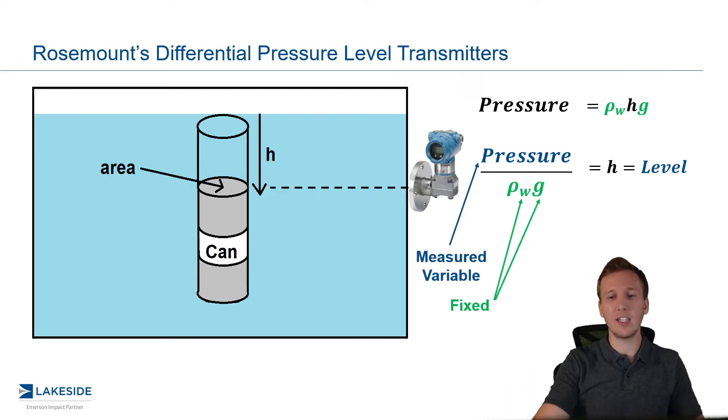Now pressure is what is called a measured variable. And then we divide it by some constant and we are left with what is called a scaled variable. It's important to understand this because if we are measuring something other than water, we have to scale for the changes in density.